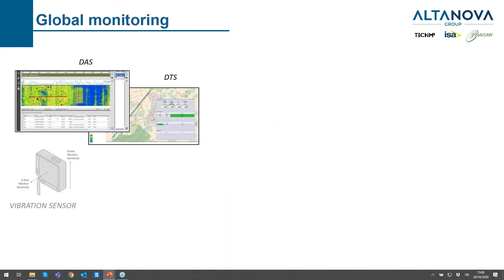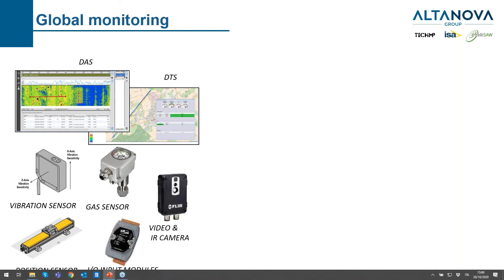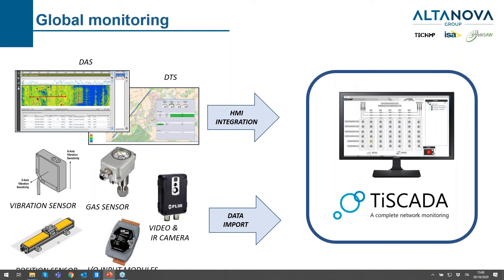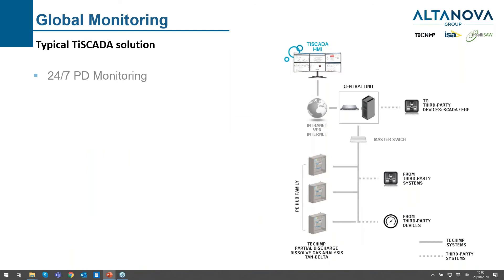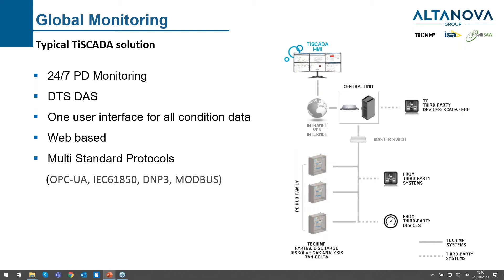We can include third-party sensors and manage other data together with the PD data. An example of HV cable global monitoring includes DTS, vibration sensors, gas sensors, video cameras, infrared sensors, position sensors, and input modules. We can do both HMI integration and data import. A typical example features 24/7 PD monitoring, DTS, DAS in one user interface on a web-based platform, with multi-standard protocols available: OPC-UA, IEC 61850, DNP3, and Modbus.